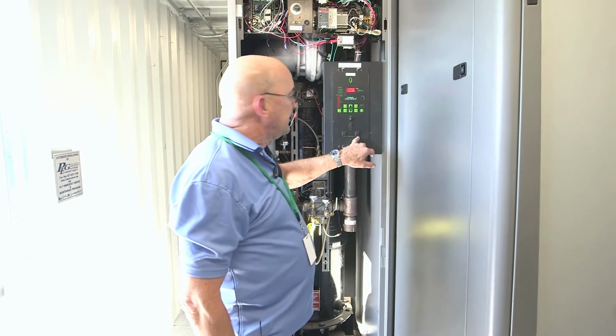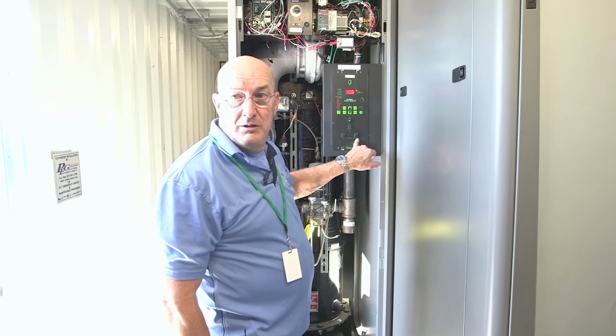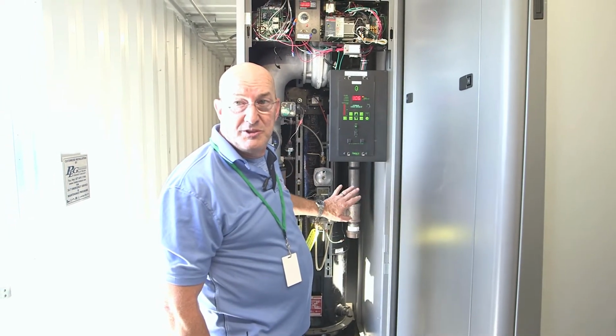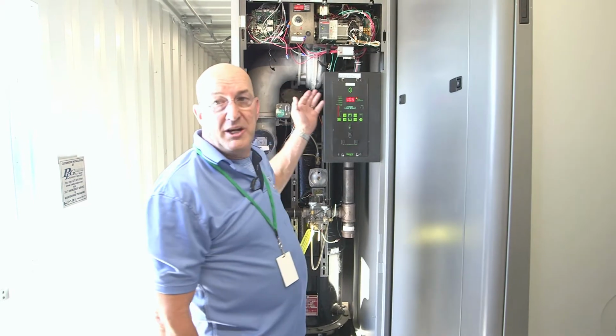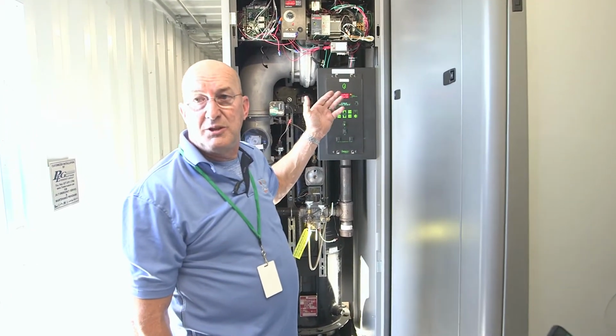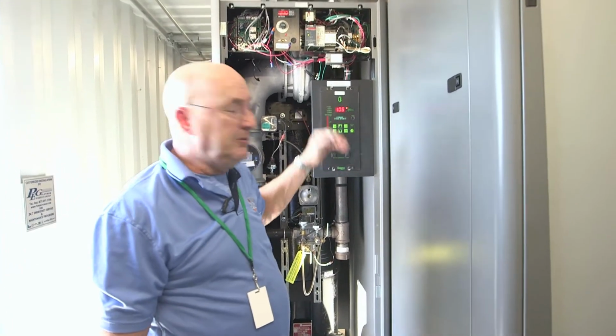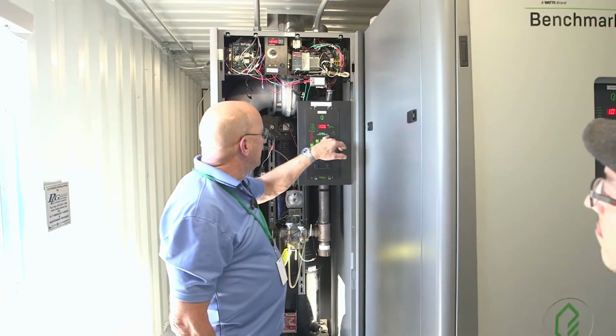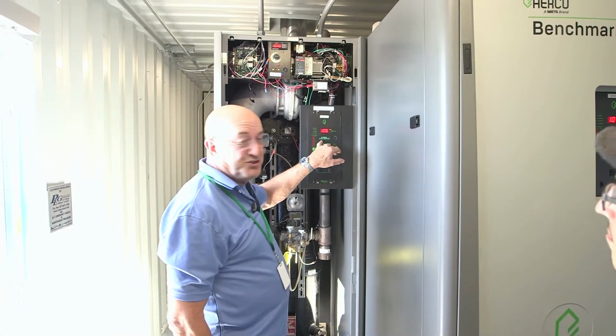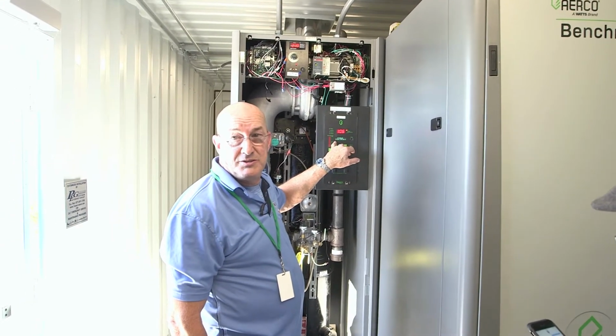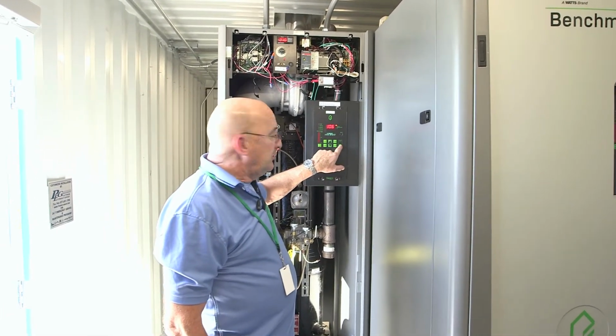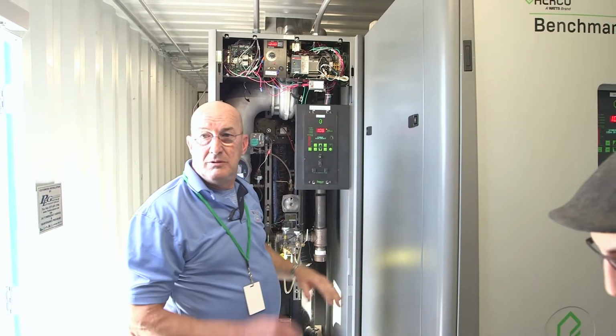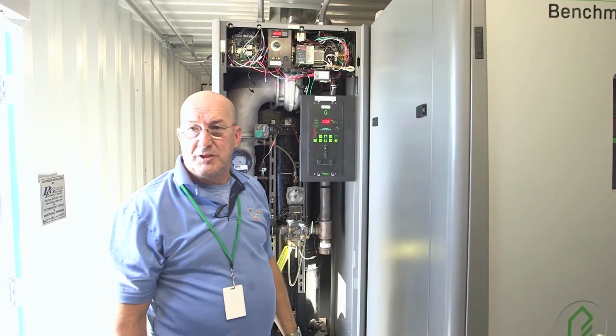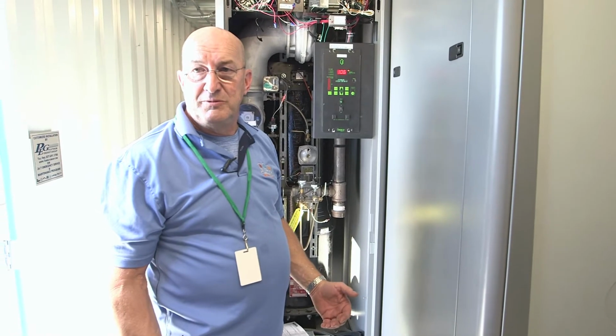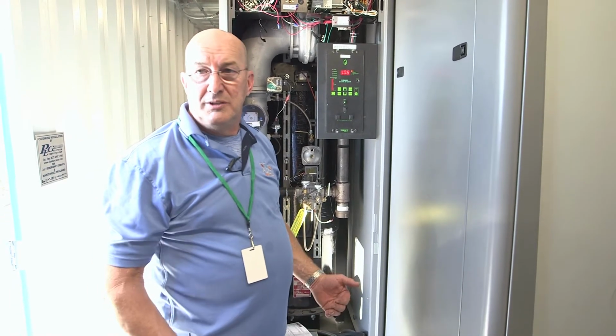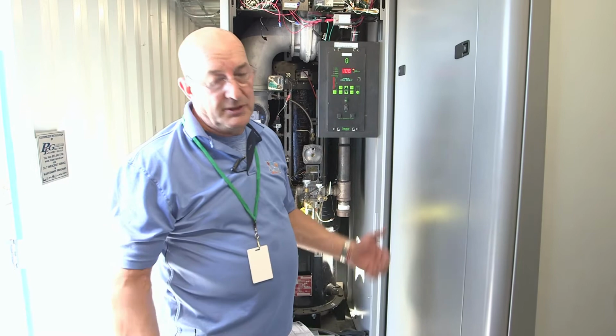If it's low water, you're going to hit this reset here, because this is one low water cutoff that's built into the boiler. And when we go around back, I'll show you there's a second low water cutoff that can be reset from the back of the boiler. But any faults will give you a fault, with the time, date, and what it is. You can hit the clear button. It'll go through a recycle. It'll try to start up. If the fault has fixed itself for whatever reason, the boiler will light and start up. If it hasn't, again, you've got to call for service.